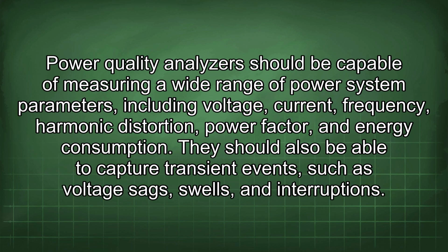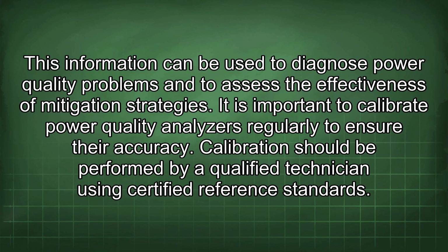Power quality analyzers should be capable of measuring a wide range of power system parameters, including voltage, current, frequency, harmonic distortion, power factor, and energy consumption. They should also be able to capture transient events, such as voltage sags, swells, and interruptions. This information can be used to diagnose power quality problems and to assess the effectiveness of mitigation strategies.